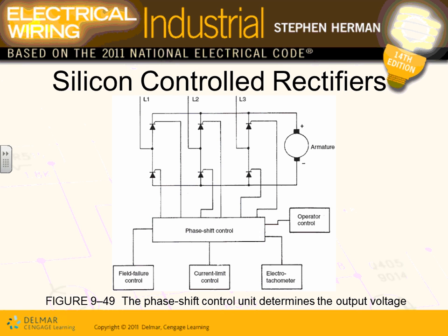Here's the rectification. There are different technologies that they can use, guys, and I'm not going to get into them. You're going to see SCRs. SCRs are one of the technologies that they use to rectify, versus diodes. And here are all the controllers in the phase-shift control. And ultimately, when you have a drive, guys, the DC drive takes the AC, converts it to DC, and allows you to tweak the DC so you can control the speed of the motor.